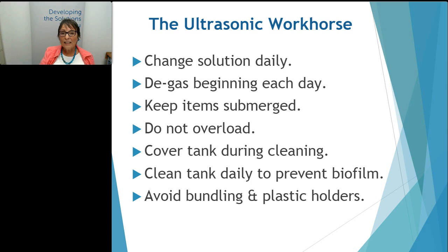So the ultrasonic needs to be emptied, cleaned out, and cleaned out mechanically as well as rinsed. That means some scrubbing action is required, because remember, biofilm is very sticky, like glue. So you can't just rinse it out. You have to actually scrub it. It's kind of like the biofilm that forms on the bottom of your kitchen sink. I personally hate this, but it is what it is. You keep adding germs, we keep adding water, and then we create biofilm.